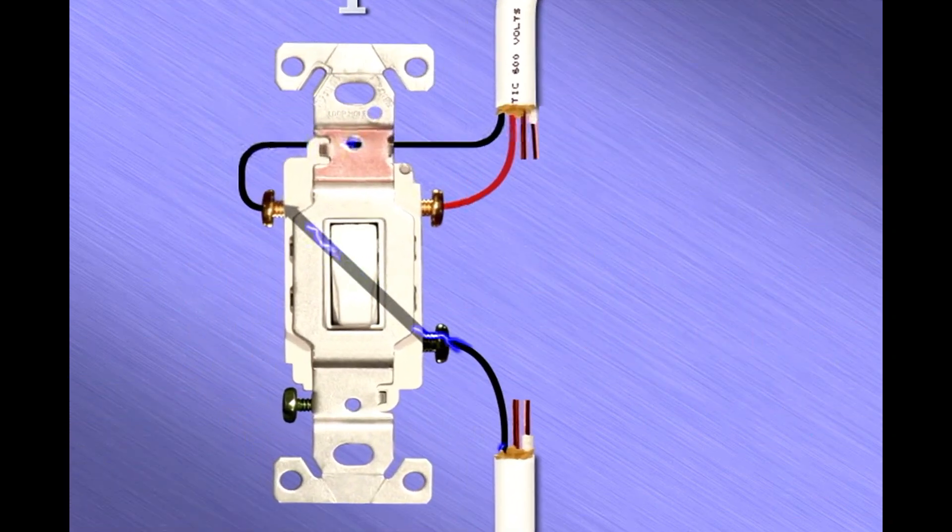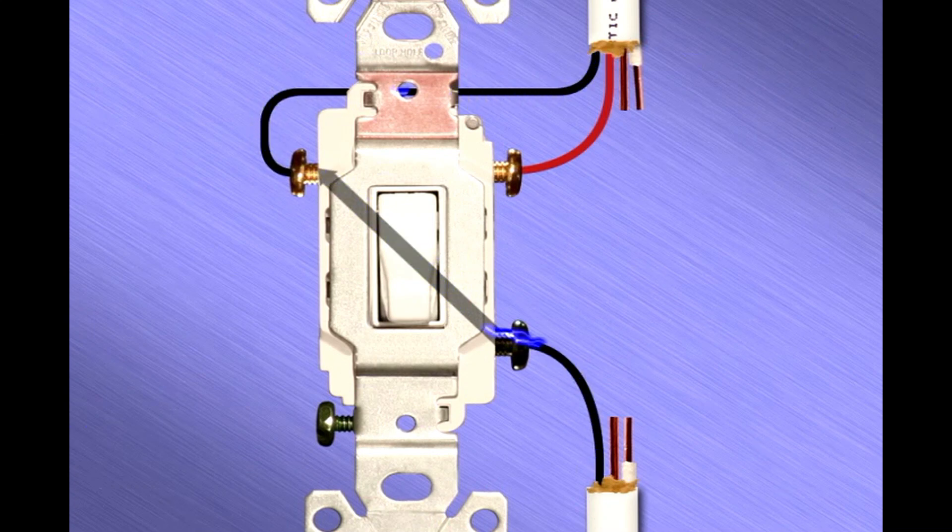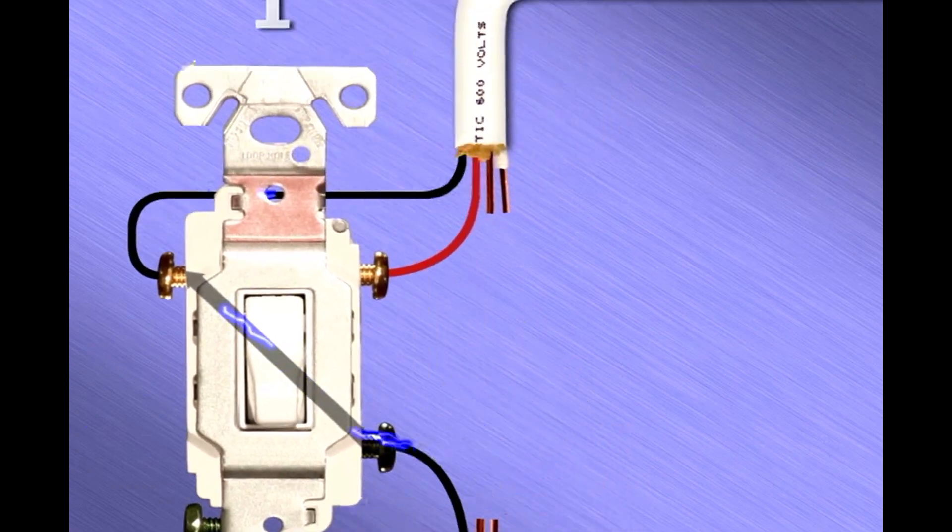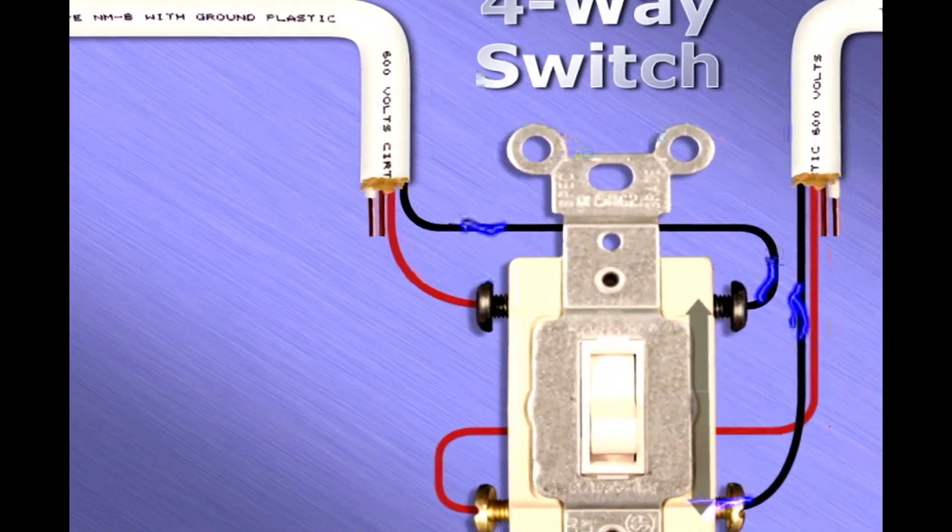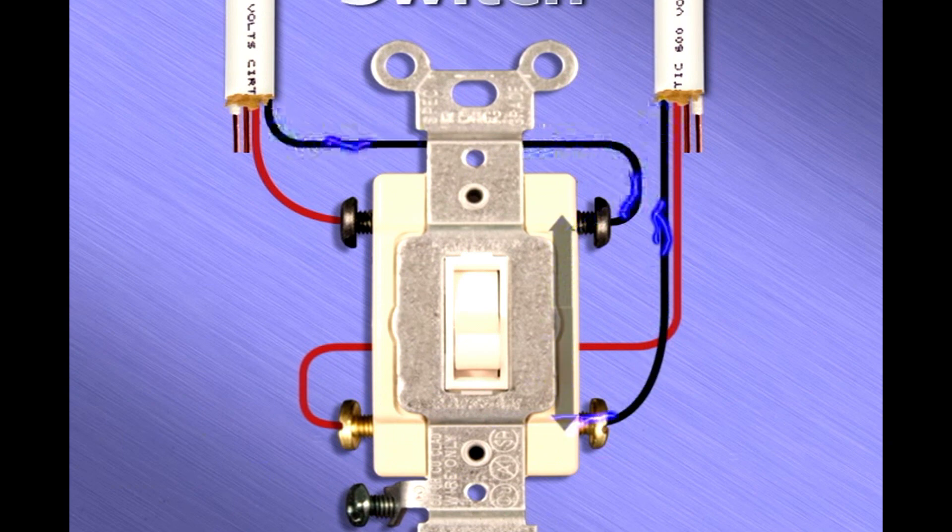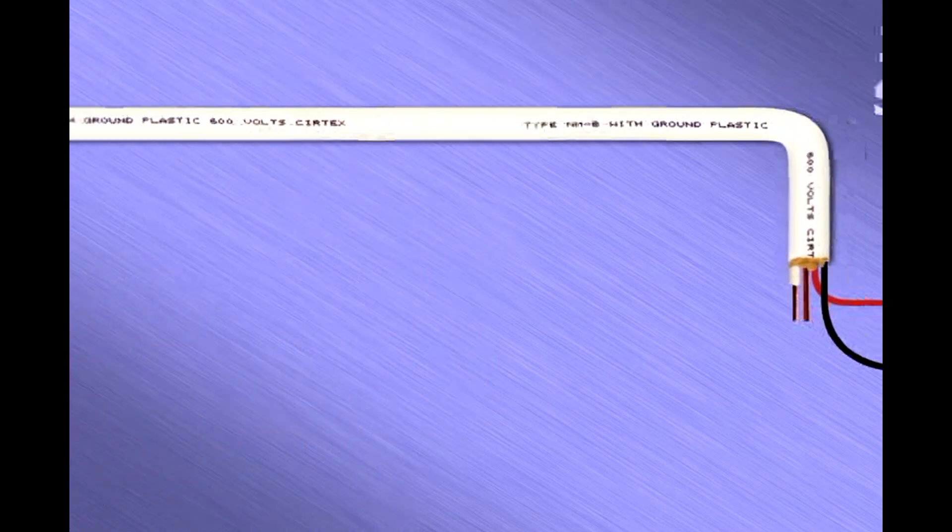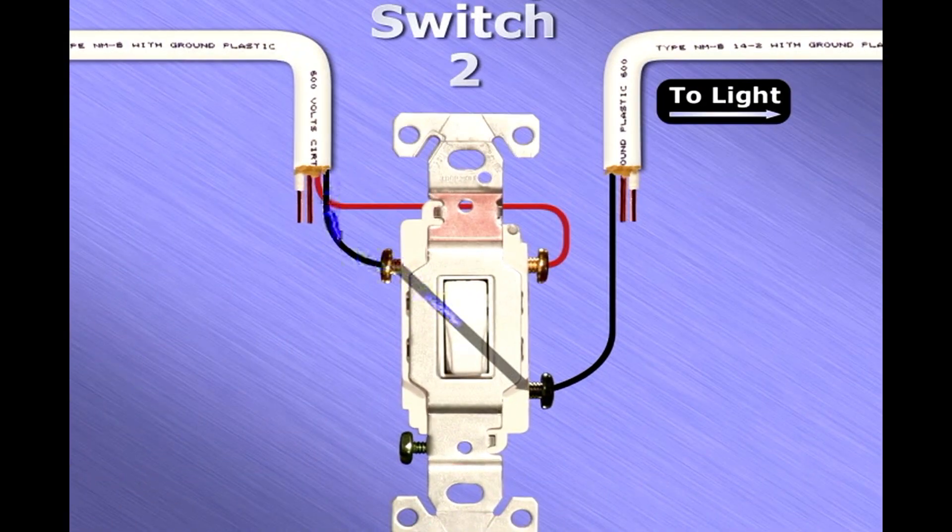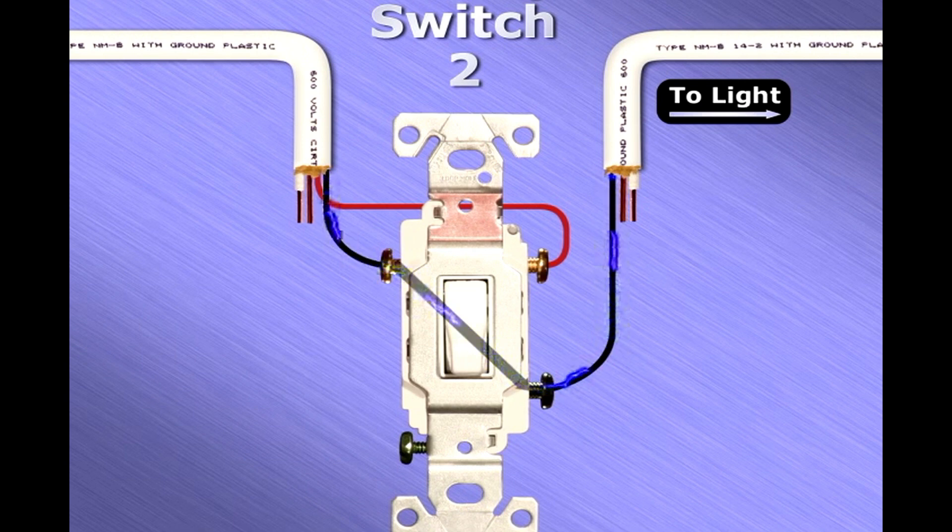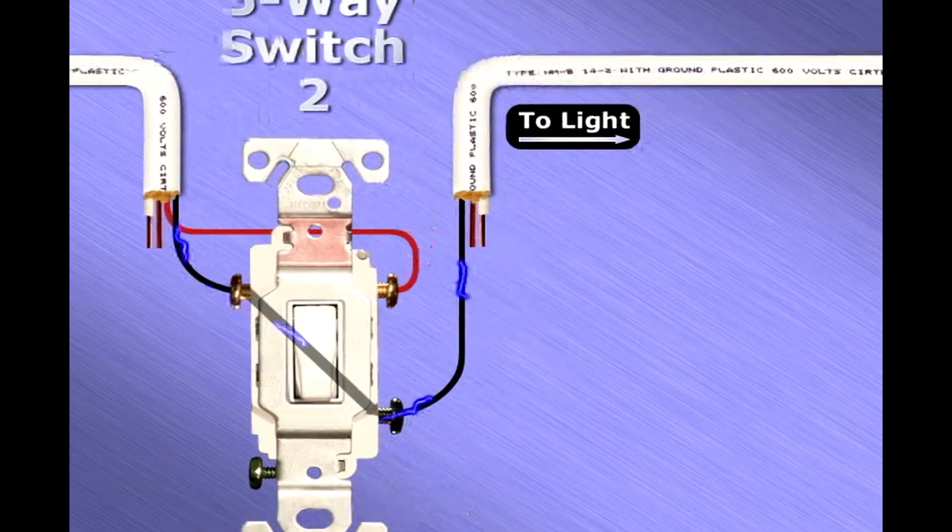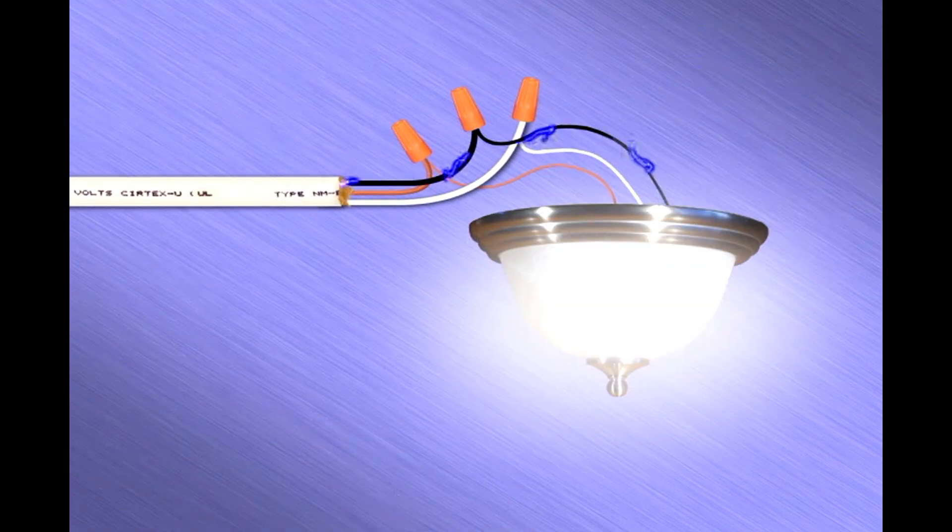Now let's see how this four way switch setup will function when electricity is flowing through the circuit. Incoming current will arrive first at the first three way switches common terminal. With the switch in the down position, the current will pass through to the left traveler terminal and travel along the black traveler wire until it reaches our four way switch. Here with the switch in the down position, the current will pass down through the switch and continue along this black traveler wire until it reaches the second three way switch. Once the current arrives here, it will pass through to the three way switch's common screw if the switch is in the down position. In this case, the current has an unobstructed path through the circuit to reach and illuminate the light.